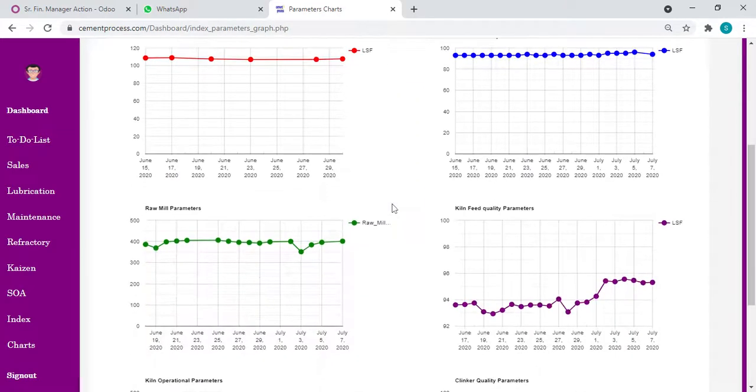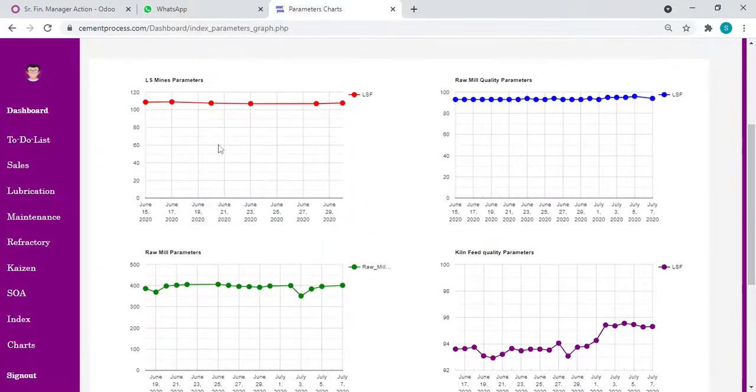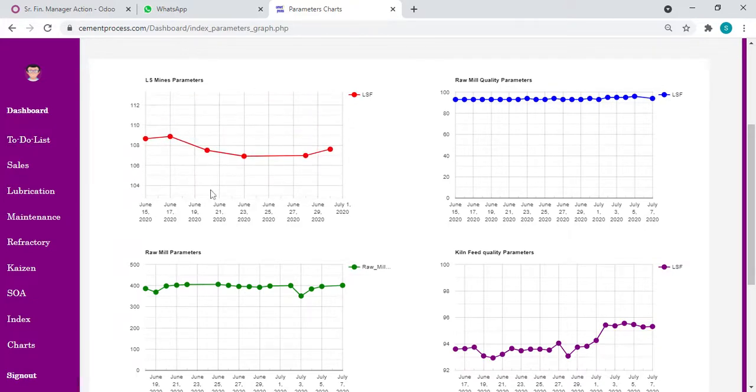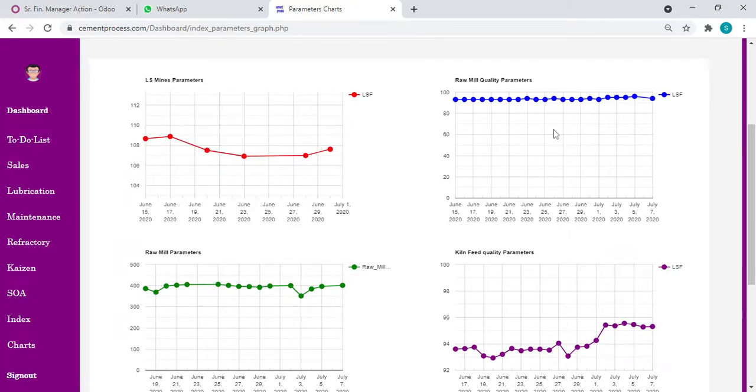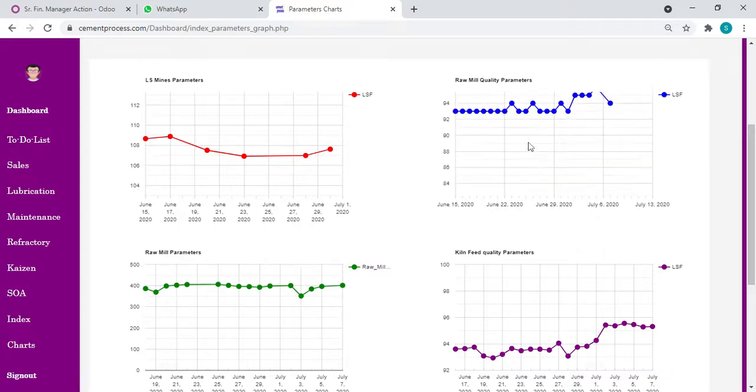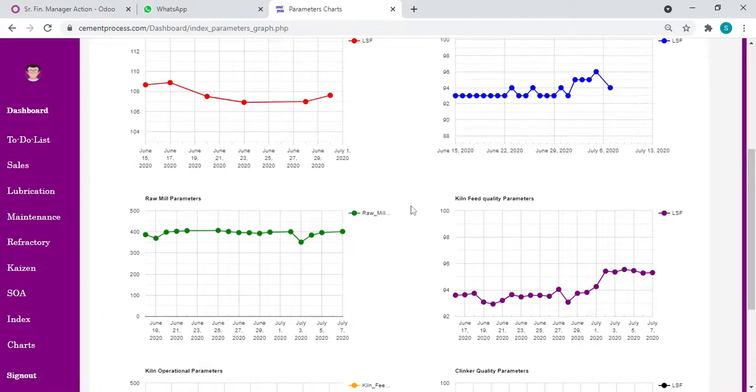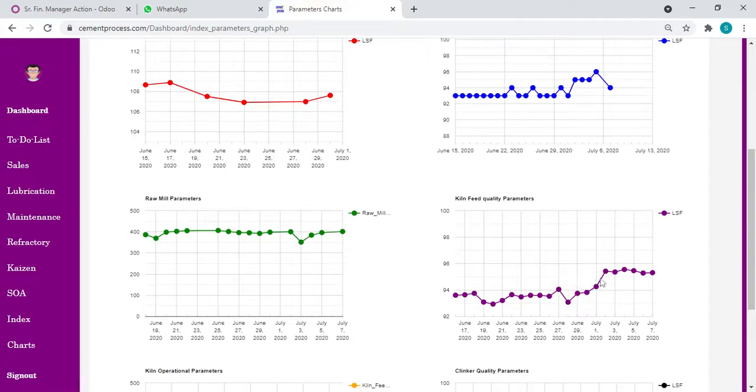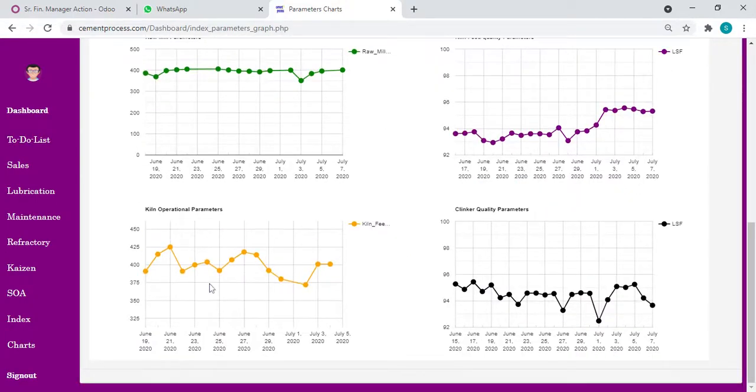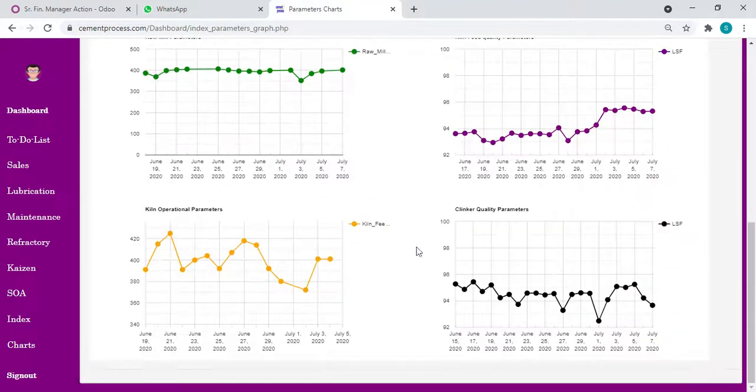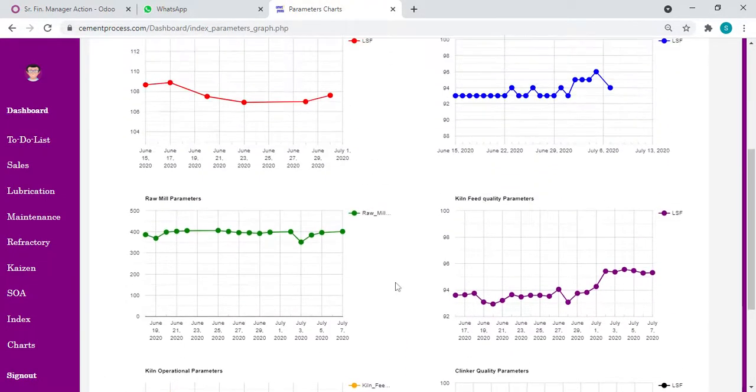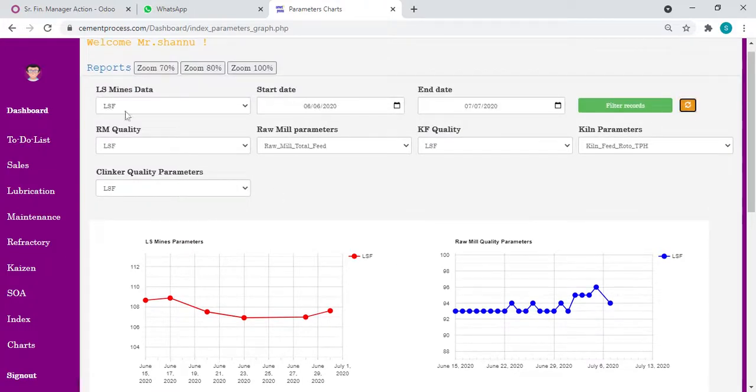Then we will get the graphs like this. Limestone mines, raw mill quality. Here in the limestone mines, I observe LSF is almost constant. Let's look at raw mill quality LSF from June 29th - from 93 going up to 96. So what is the effect of raw mill LSF on the kiln feed? We can see the same increasing trend in the kiln feed also. Then the kiln feed started decreasing - 392, 380, 372. What I'm trying to make you understand is in a single click, in a single view, we can view all the parameters, compare, and take necessary corrective actions.